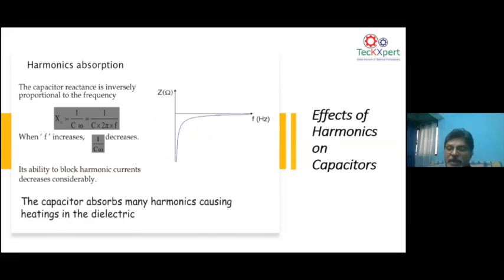Now, when there are harmonics in the network, the capacitance absorbs the harmonics because capacitive impedance is 1 by 2 pi Fc. Here F is the frequency, and the higher the frequency, the lower the impedance. Because of this 1 by 2 pi Fc relationship, the capacitor becomes a sink for harmonics. It starts absorbing them because it becomes a low impedance path for harmonics.